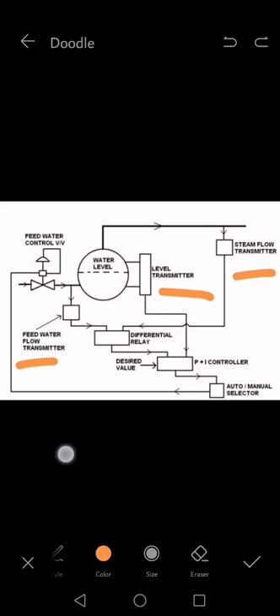This brings the water level back to the normal level and balances the steam flow and feed water flow. I hope your doubt is clear. There is also an auto and manual selector provided. If sometimes there's a problem in the automation control or delay, or if the P+I controller has a problem, we can put the valve in manual mode.